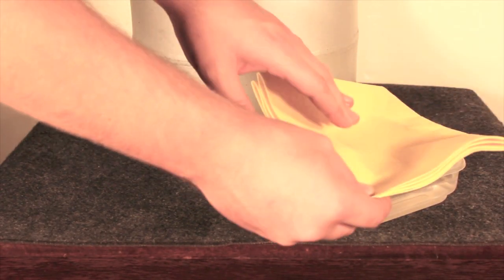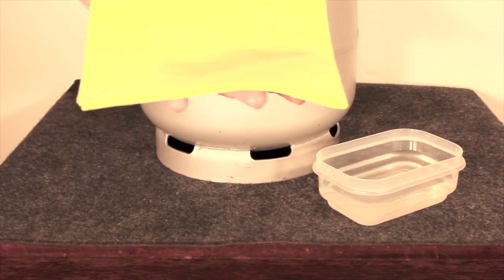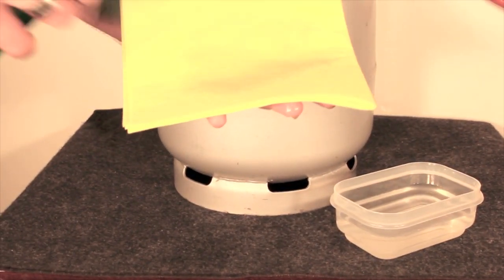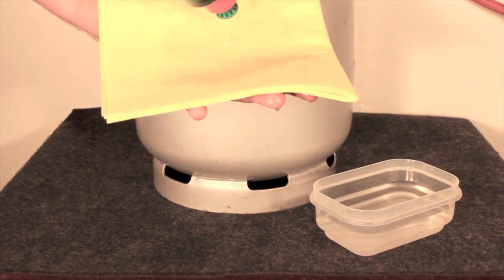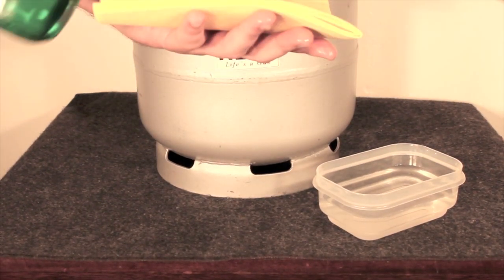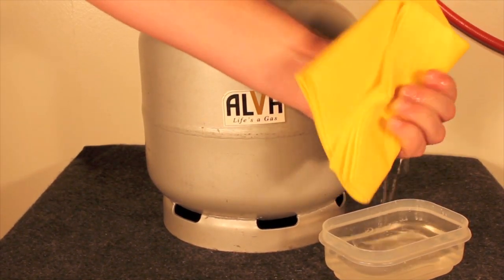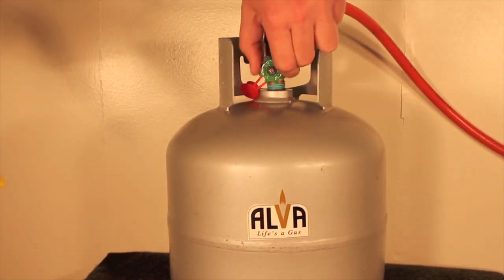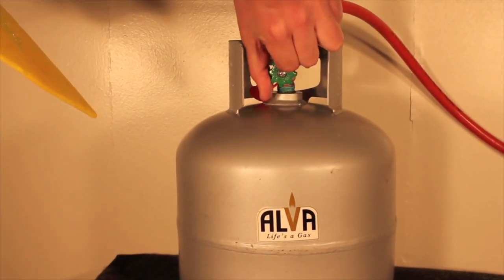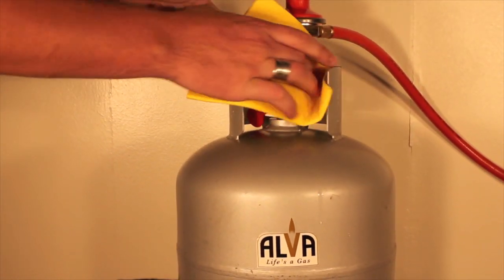Use one part soap, one part water solution to wipe down all connections. Open the cylinder valve 1.5 turn and proceed to do the leak test.